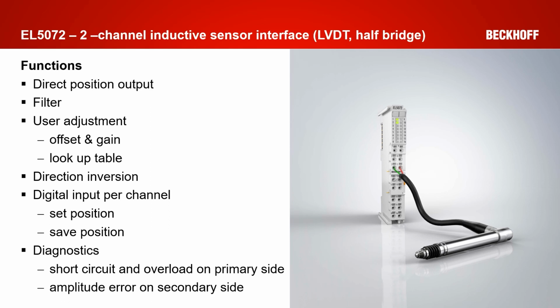But of course, you still have some correction possibilities for the signal. It could be some filtering of the signal, but also an adjustment, just a simple one via offset and gain parameters, and a lookup table with up to 20 entries is also implemented. If you connected, for example, the power supply in reverse polarity or just mounted the probe upside down, you can use the direction inversion bit to reverse the connection. So a plus position can become a minus one.